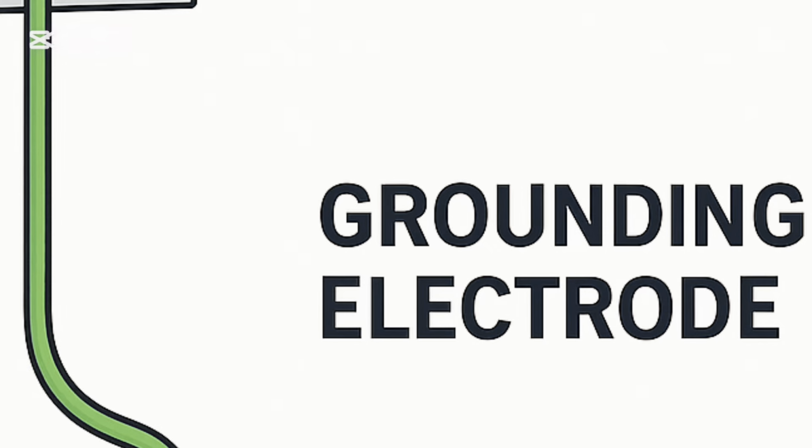First, let's clear the biggest confusion of the grounding electrode system. Rod, plates, concrete encased, whatever: it does not trip breakers. It is not a fault clearing path. It is grounded. It is not bonded.